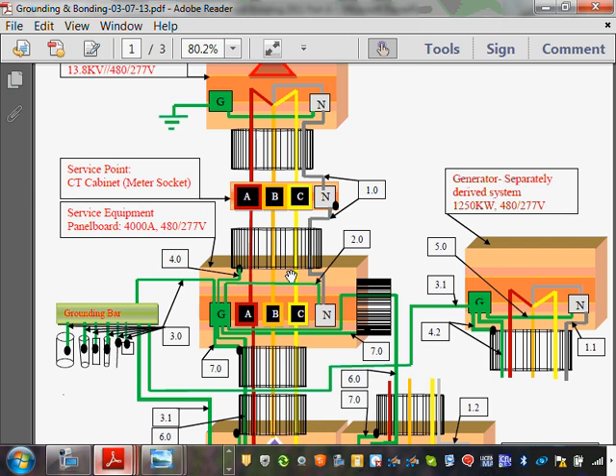Here's the catch-22 though. If you have steel or a concrete encased electrode, you're done. One of them satisfies the grounding electrode system. The catch-22 says if you have other grounding electrode systems in your building, you must bond to them. That's how you end up with a steel building. You tie to the steel, you tie to the water, you drive a ground rod, especially in bigger systems.